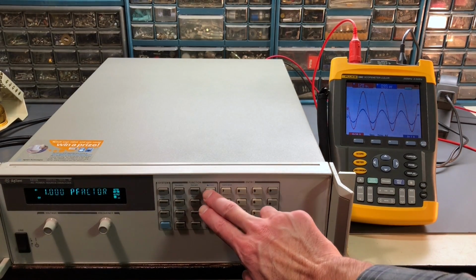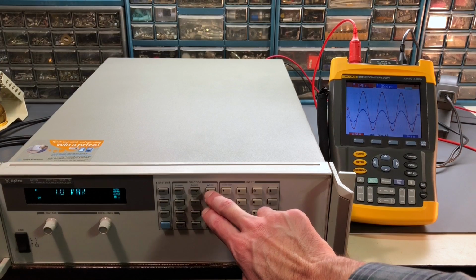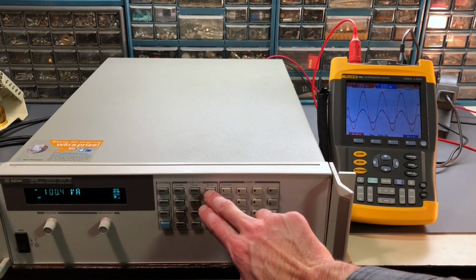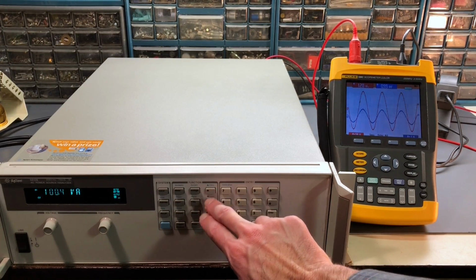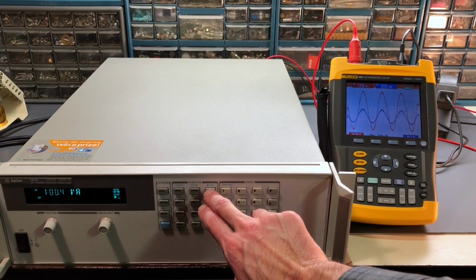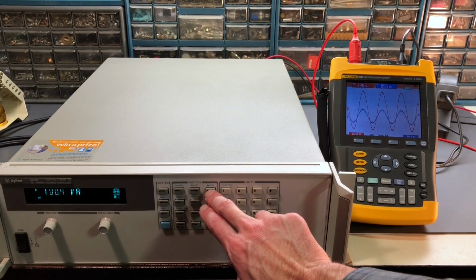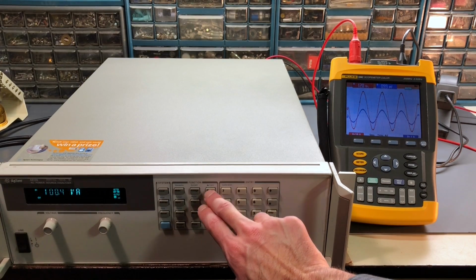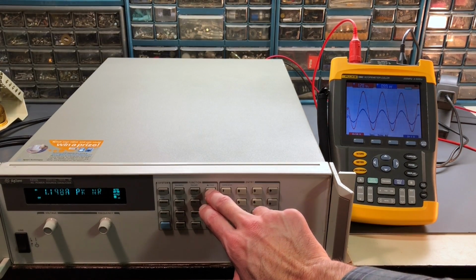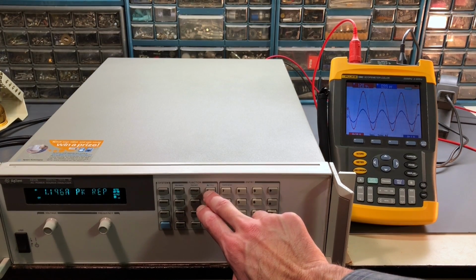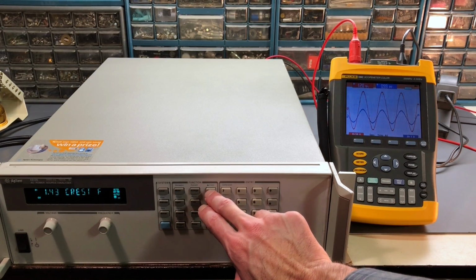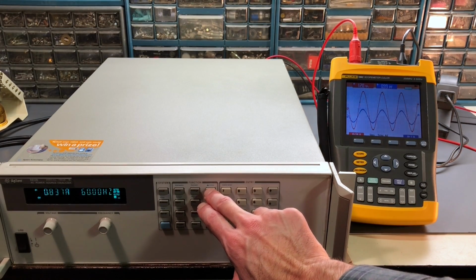You can scroll through some of the other readings that are on here. You can see volt amps reactive, or reactive volt amperes, 1, makes sense. See the VA rating 100.4, 100.5. So the VA rating, volt amperes, would be the same as the wattage on a resistive load. Did I go past that? Nope, there it goes. Okay.